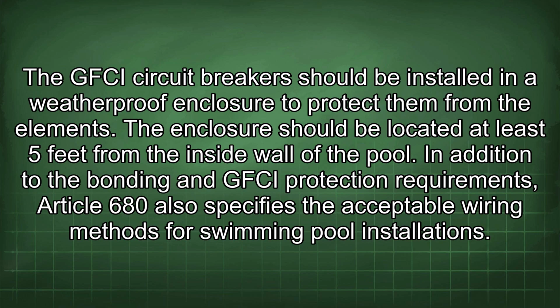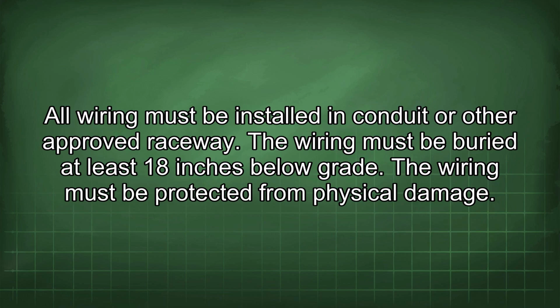In addition to the bonding and GFCI protection requirements, Article 680 also specifies the acceptable wiring methods for swimming pool installations. All wiring must be installed in conduit or other approved raceway. The wiring must be buried at least 18 inches below grade. The wiring must be protected from physical damage.